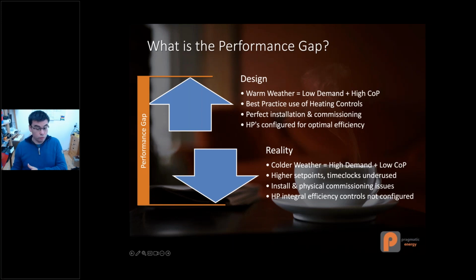In reality, it's probably colder outside. People have probably left their set point at 23 or 24 degrees one day, or left the cylinder on a boost temperature. Time clocks tend to be underused. There are issues all the way from a valve not being fully open, so the heat pump doesn't get the flow rate it needs and is a bit less effective, to all the integral controls designed over the last 20 or 30 years to make heat pumps as efficient as possible being left in the most conservative setting - meaning they're not really doing much to increase performance or reduce demand in the house.